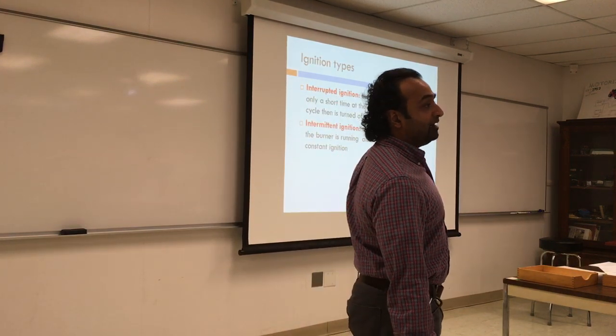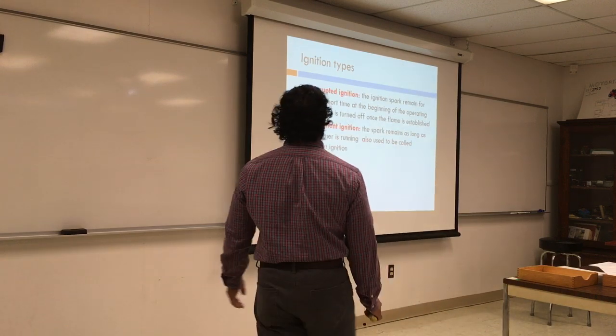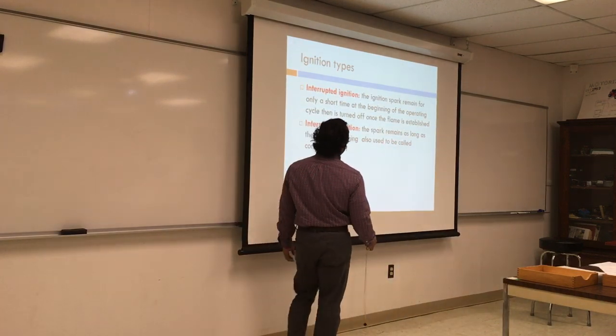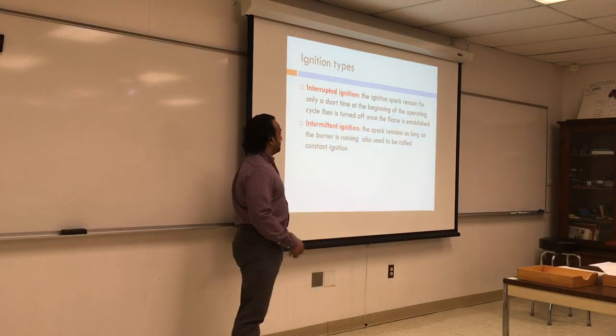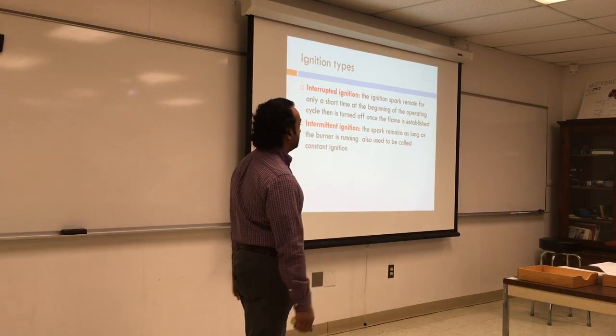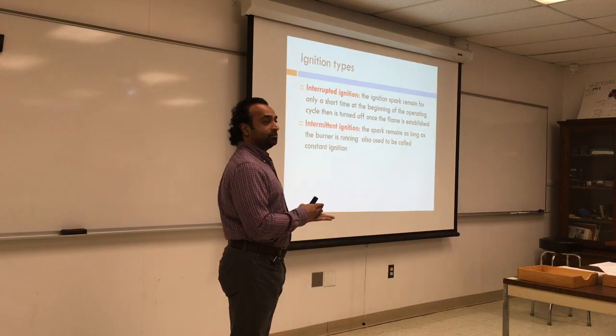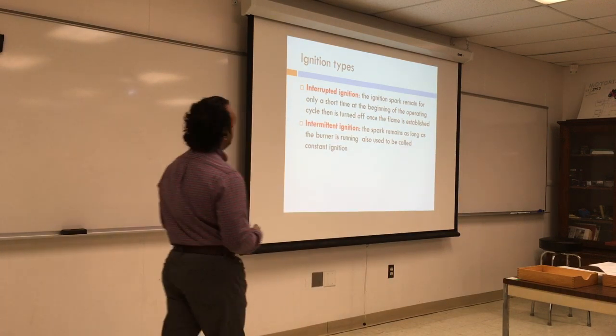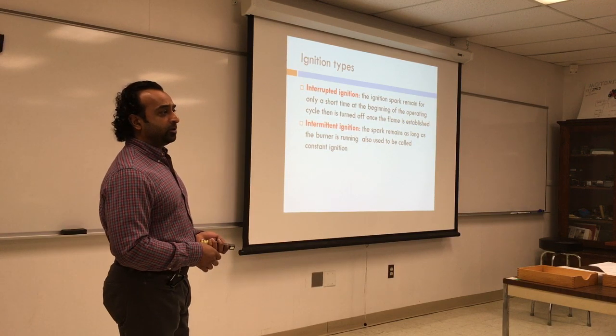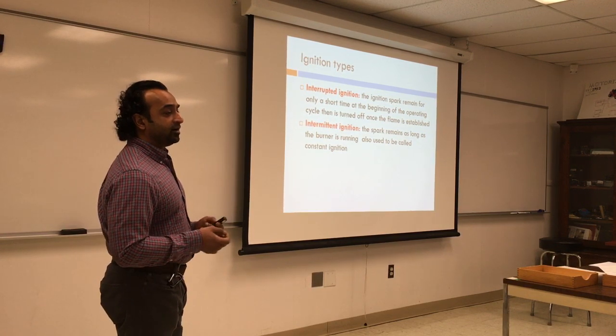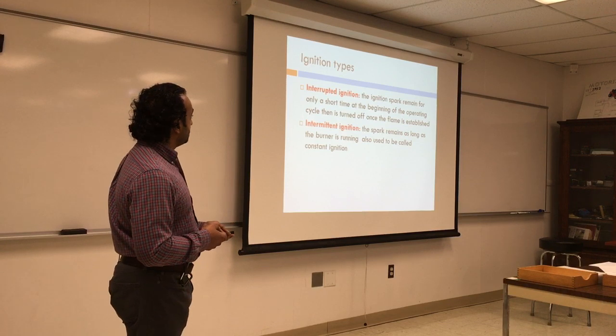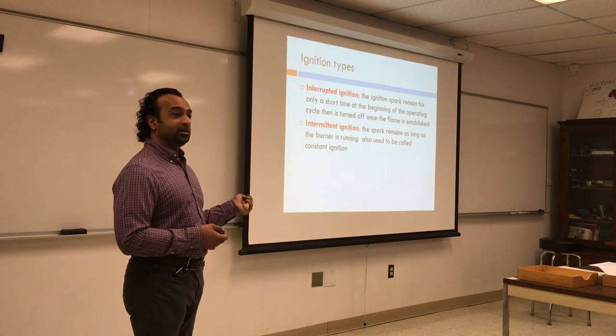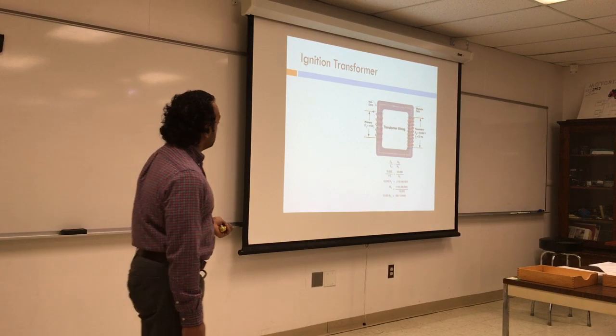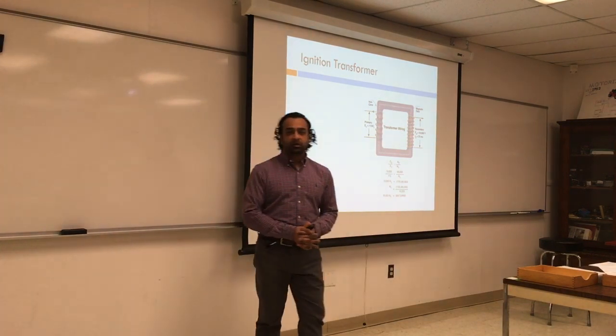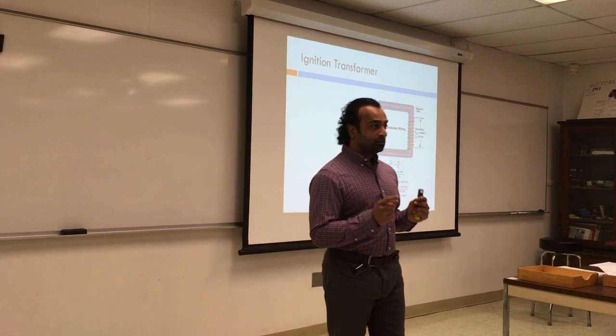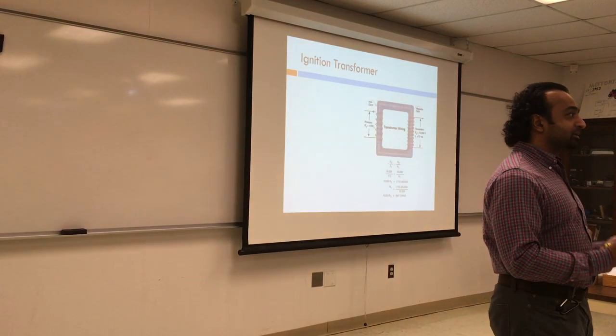Some old models still have constant ignition, but it's not the code. For intermittent, the spark remains as long as the burner is running, and it's also called constant ignition. Interrupted will stop. Intermittent will continue. We don't want the intermittent one because it's just wasteful. Once the fire is going, the ignition should go off. Make sense? Clear? Okay.